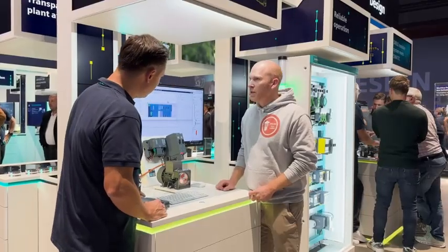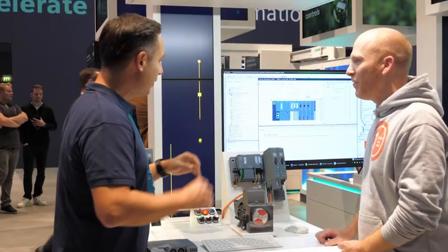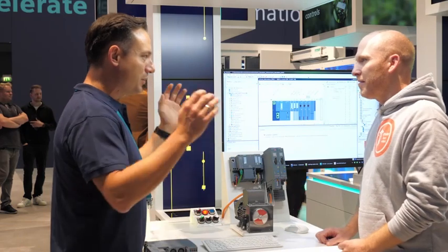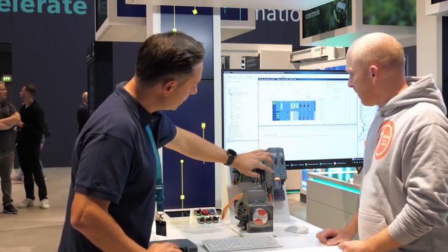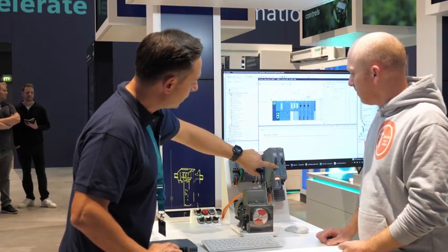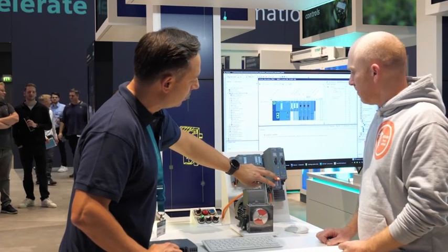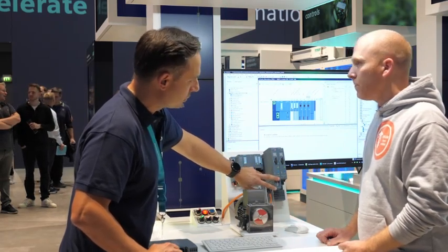Yeah, normally you would expect some flash or something. You would see the lights flickering or somebody running out and saying, hey, what have you done? My fuse got blown out in the back. So you see here the diagnostic. The short circuit LED is lighting up, and it's telling you here on the load side, this is the load side LED, that there is a short circuit happening.